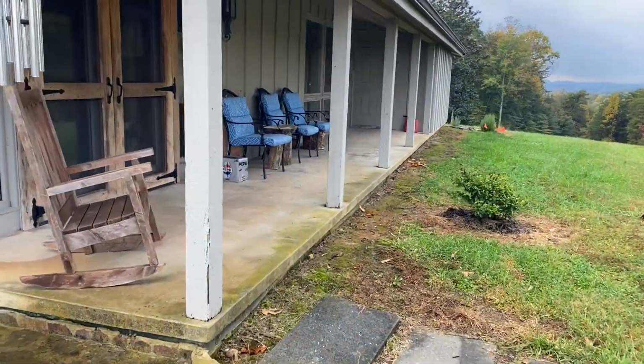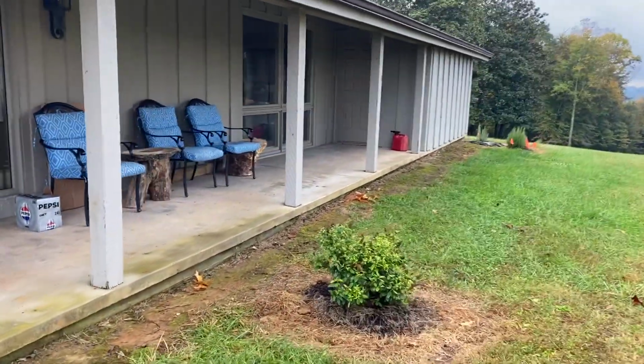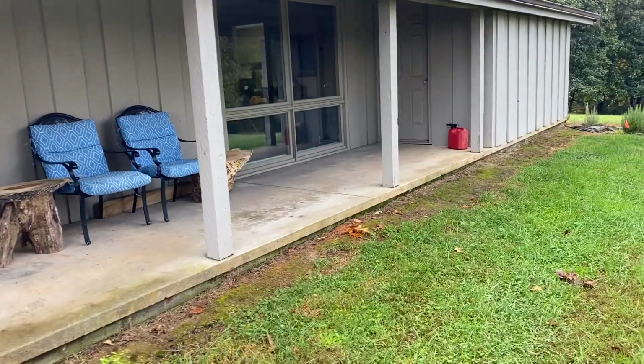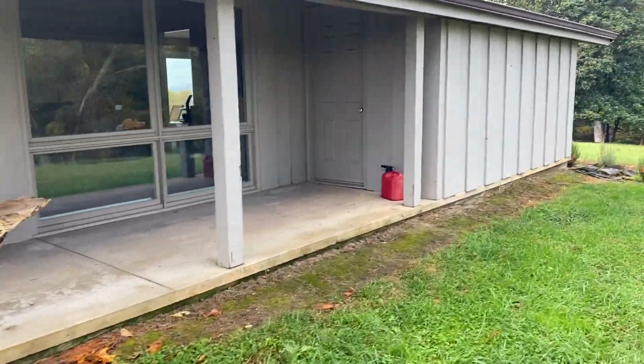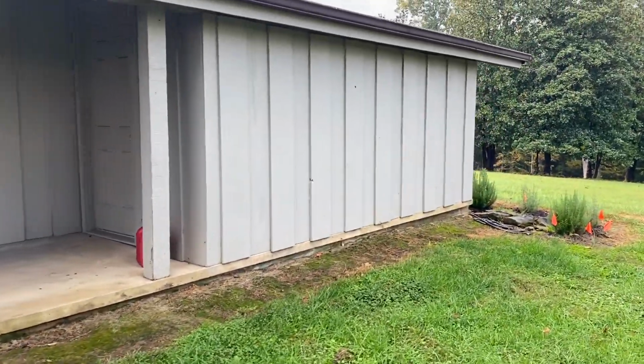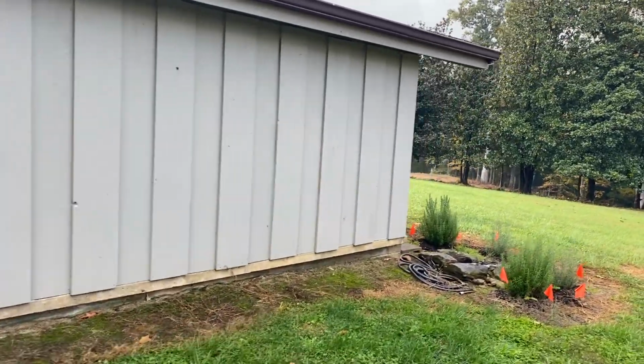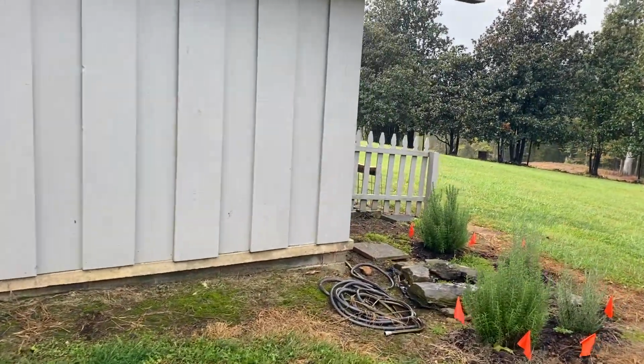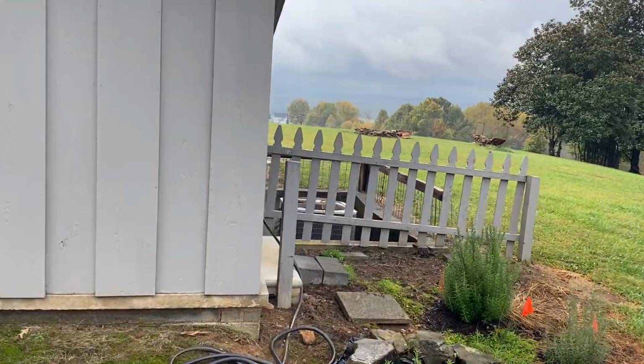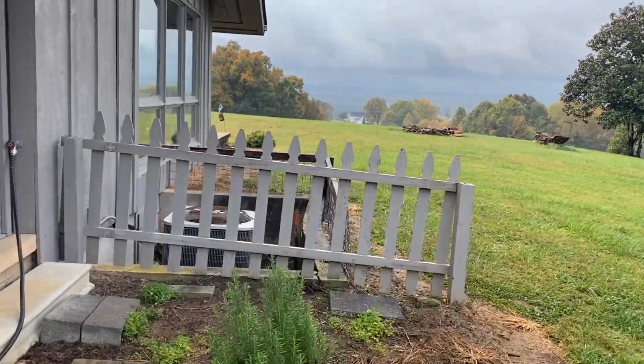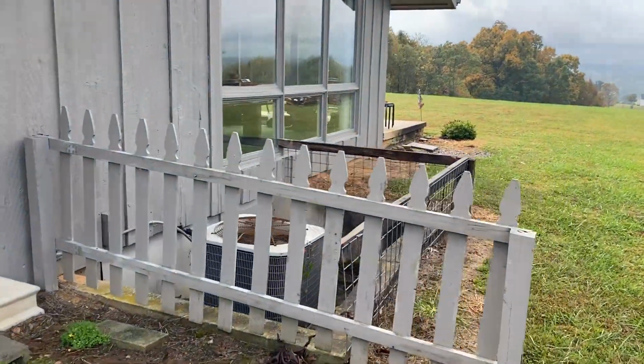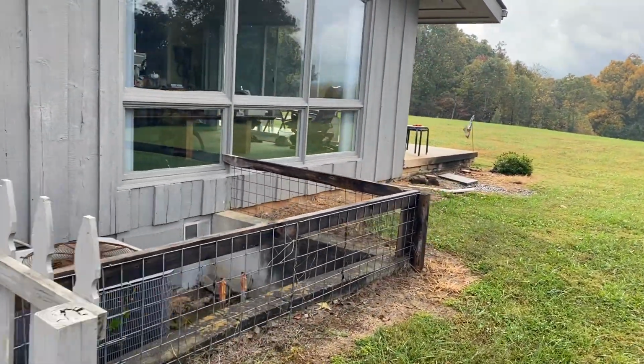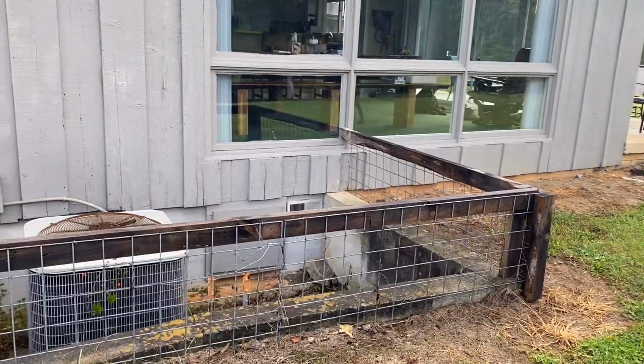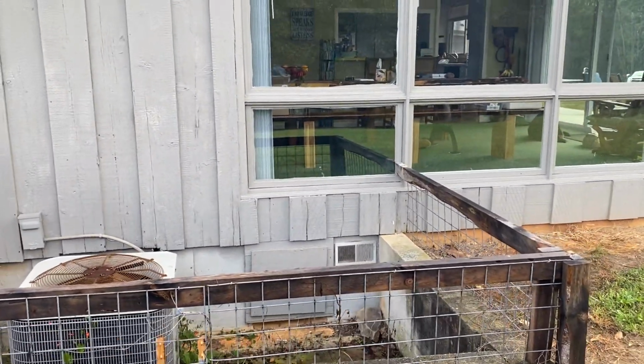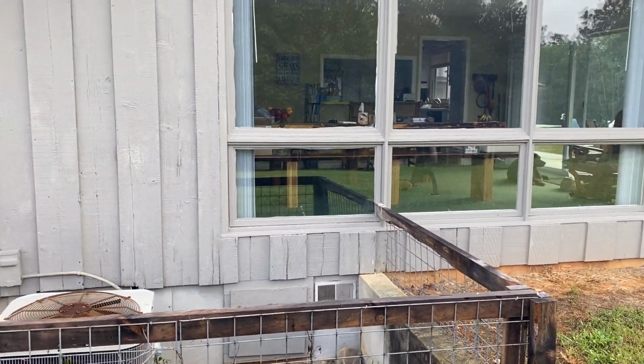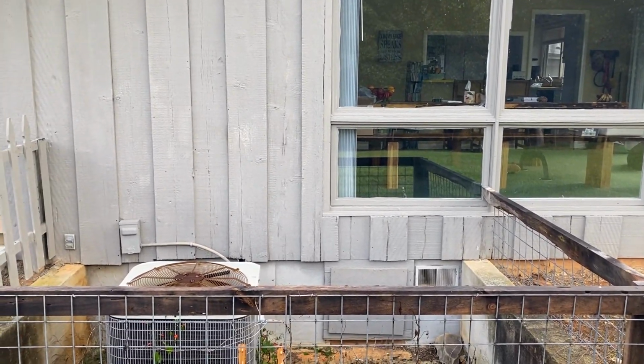So our plan is that since the 360,000 that can come out of the furnace is way more than needed, even with inefficiencies such as water flow and airflow through the heat exchanger, if I got a couple of 100,000 out of this heat exchanger, it would still be way more than needed. So I'll probably put a second one in the unit that services the bedrooms later, but for now I'm going to put it in here.